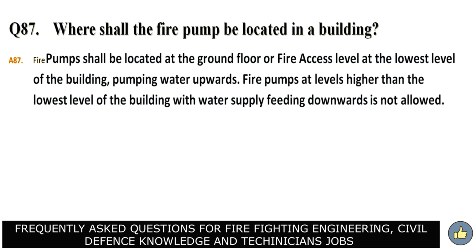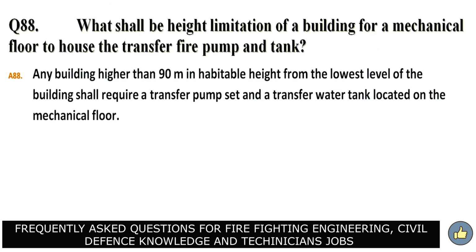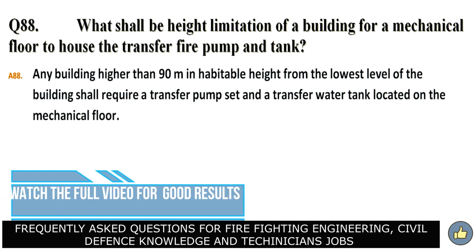Where shall the fire pump be located in a building? Answer. Fire pump shall be located at the ground floor or fire access level at the lowest level of the building, pumping water upwards. Fire pumps at levels higher than the lowest level of the building with water supply feeding downwards is not allowed. What shall be height limitation of a building for a mechanical floor to house the transfer fire pump and tank? Answer.